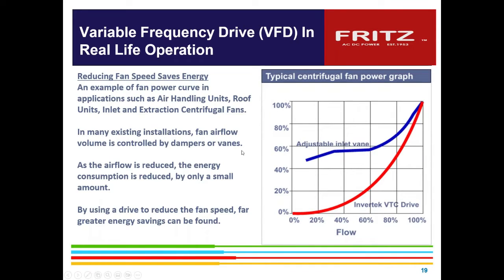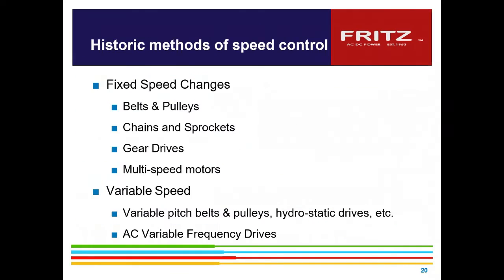A lot of them are going on rooftop air conditioning systems now, where they're putting VFDs on both the inlet and outlet fans, and they're also putting VFDs all the way down to the compressors, controlling the compressors back to temperature instead of just running them. A lot of it before, they were utilizing belts and pulleys to get it to run at the optimal speed.